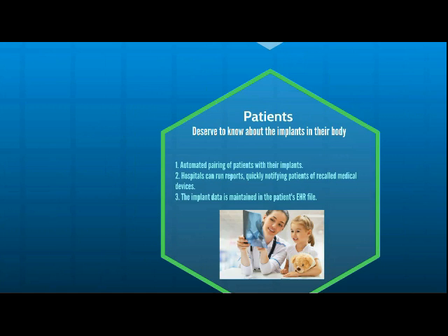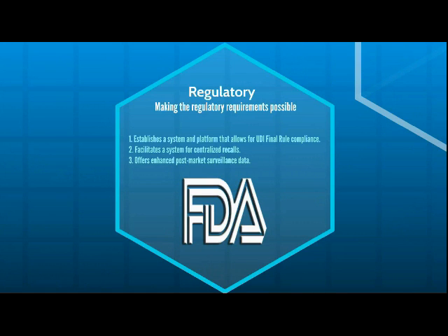Regulatory: from the FDA's perspective, it's really great to have a direct part mark on items, but it's even better if we take that data and can do something with it. That's why this is important: you now have accurate information on what's implanted in patients. So for recalls and for post-market surveillance of product performance, we are now able to do that.